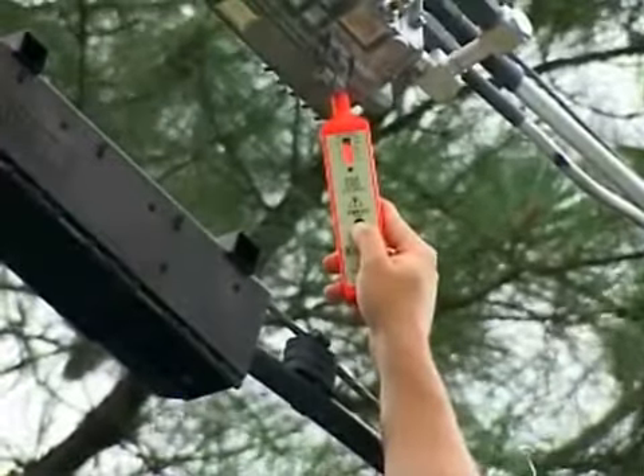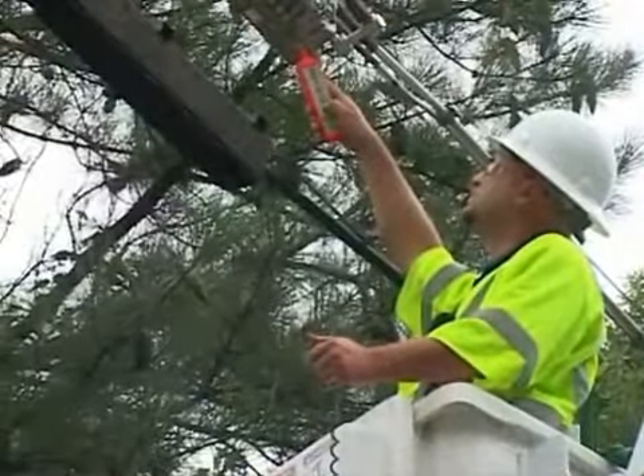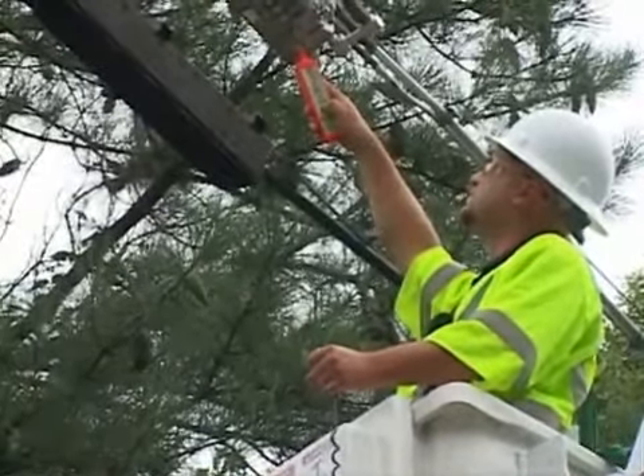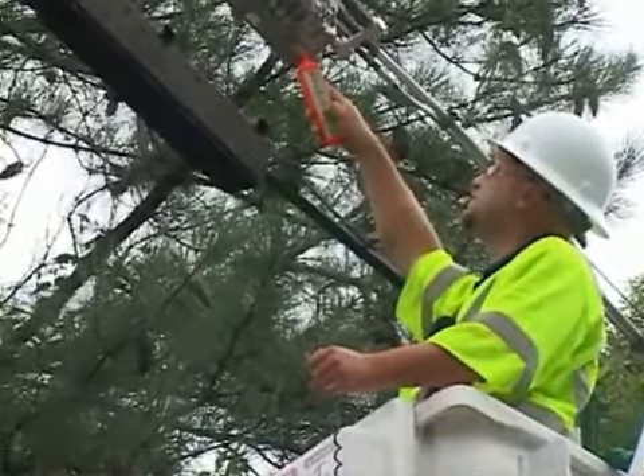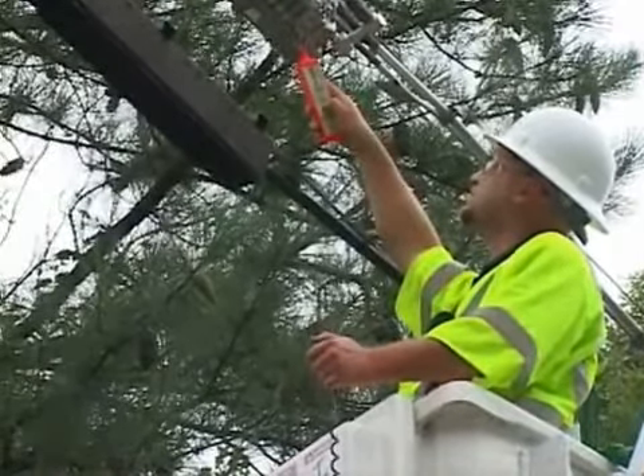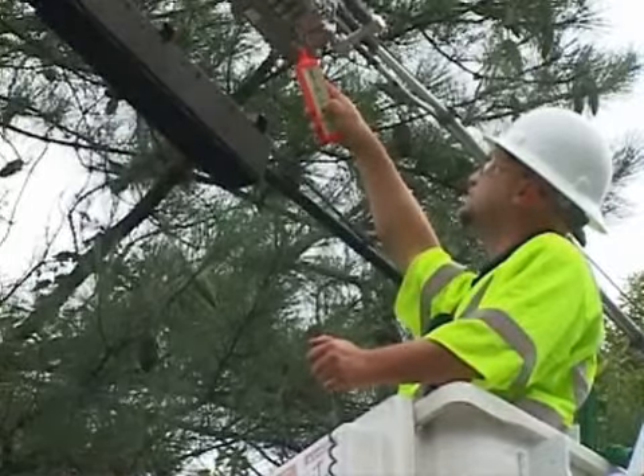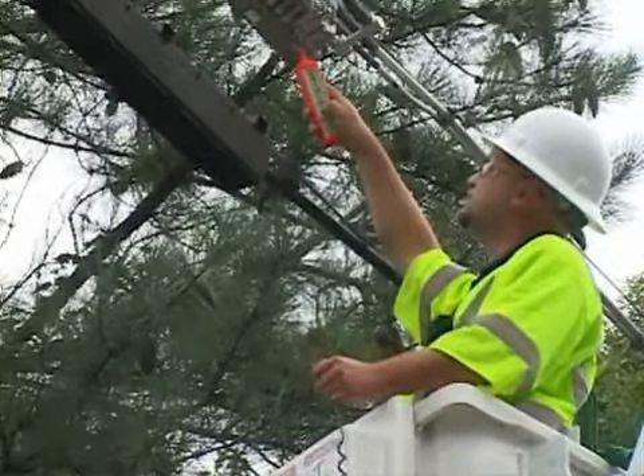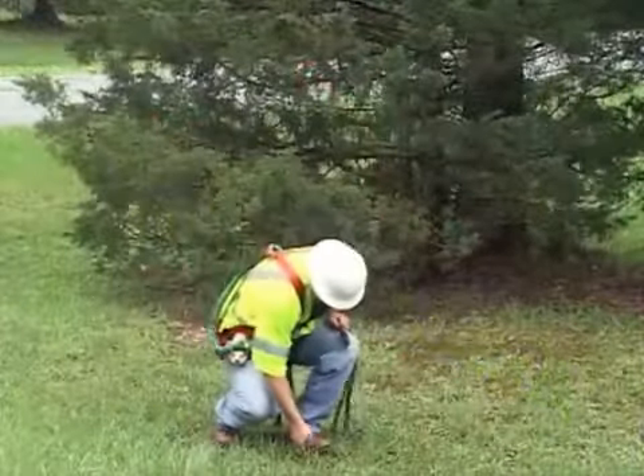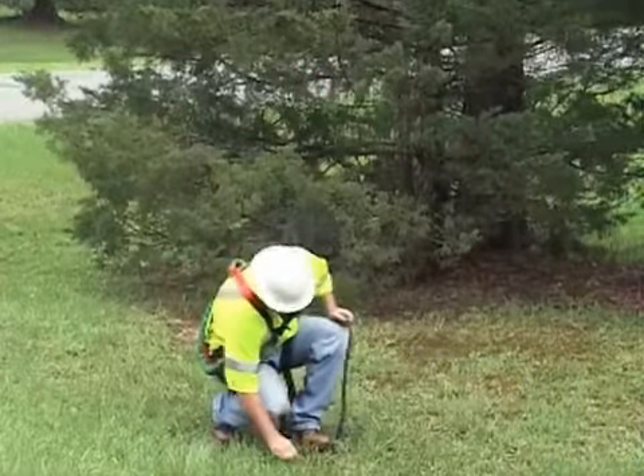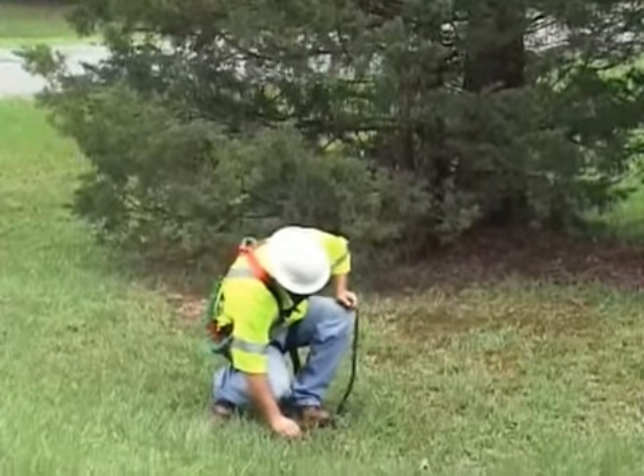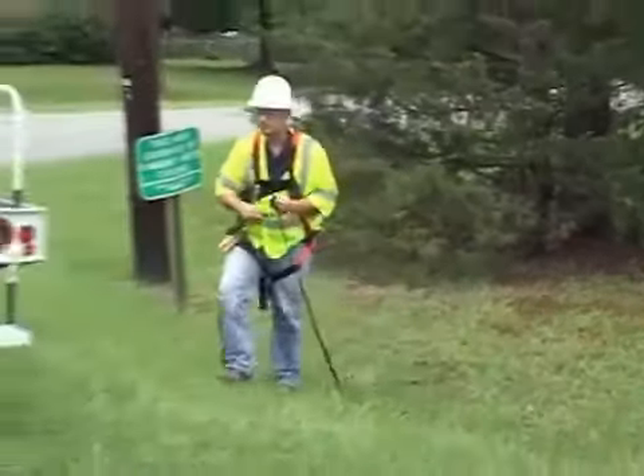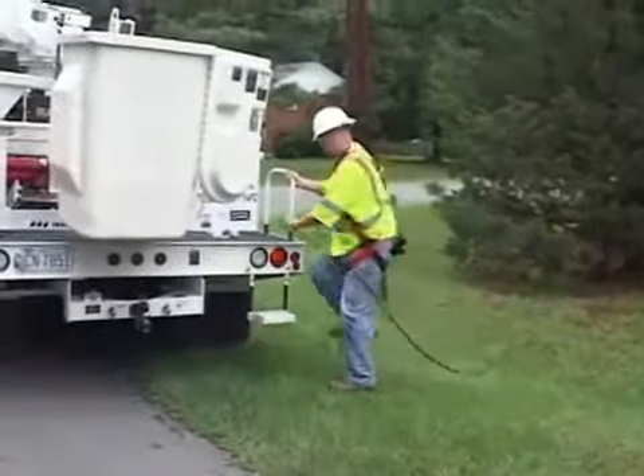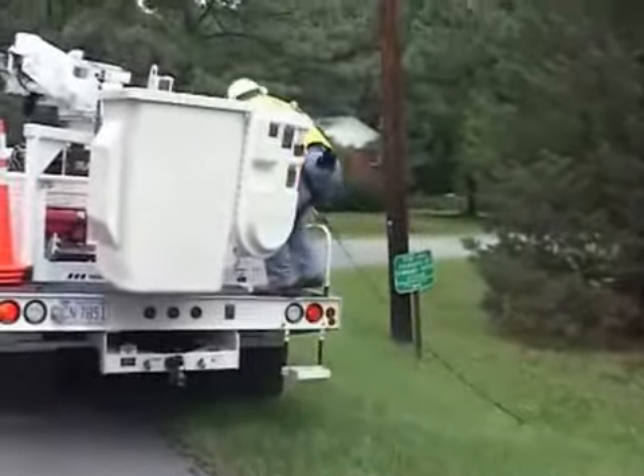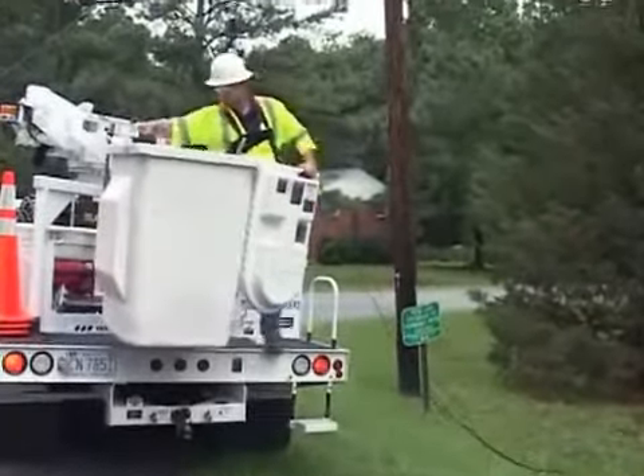To determine if this condition is actually causing a hazardous voltage indication, the user of the FVD should provide a temporary path to ground for his body in order to remove the voltage caused by capacitive coupling to the power line. The user then conducts another test. The recommended method for grounding the operator is for the operator to hold one end of a ground cord that is connected to an earth ground, a screwdriver inserted into the earth and connected to a ground cord. Do not use the vertical number 6 power ground on the pole.